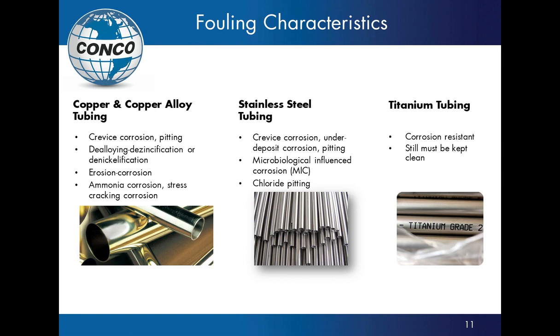If you have a stainless steel tube, manganese interacts negatively with stainless, and you can get a lot of corrosion and pitting very quickly. So you want to make sure that in a stainless tube that you remove the manganese because of that interaction. You can also end up with situations where you have two types of fouling inside the unit, where the manganese may be plating out on the inside and maybe a scale on top. So you're not really seeing the manganese, but you know that it's in there. We'll discuss how in a moment, but you want to make sure that you get it out and you're able to remove all the fouling in that tubes.